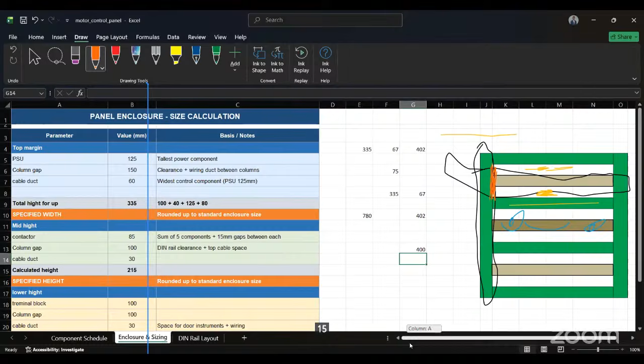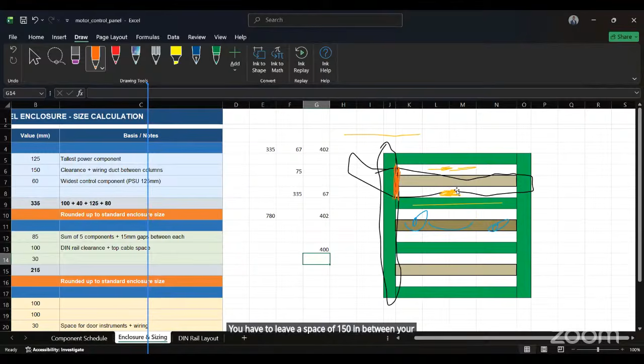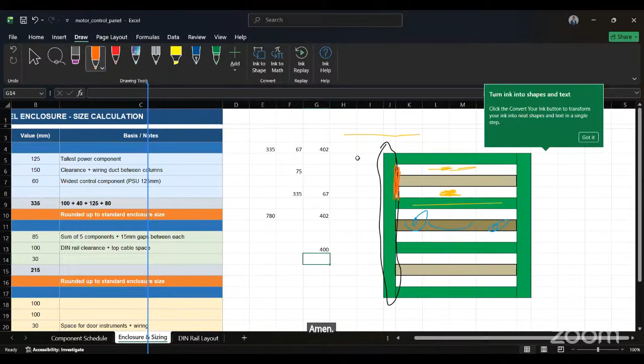Where is it? The column gap here is 150. I explained in the last class that for standard panel building, you have to leave a space of 150 in between your tray. But the minimum acceptable is 100 mm. If you can't leave 150, you have to leave at least 100 mm. So now we're leaving 150 because we have a very tall component.